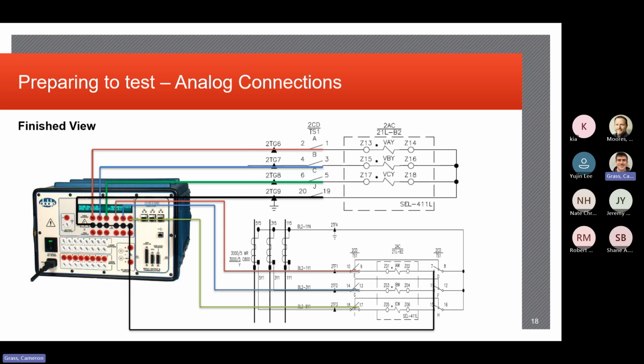usually pretty important. I like to do red, white, and blue usually in the field for phases A, B, and C on the currents and the potentials. You can switch it up however you need to, but basically the finished view is going to be your currents going into the correct inputs on the relay, your voltages going into the correct inputs on the relay, verifying your outputs by wiring in a spare output from the relay to your logic input to make sure that the test set sees that the output picks up when need be, which I'll get into in a couple slides here.